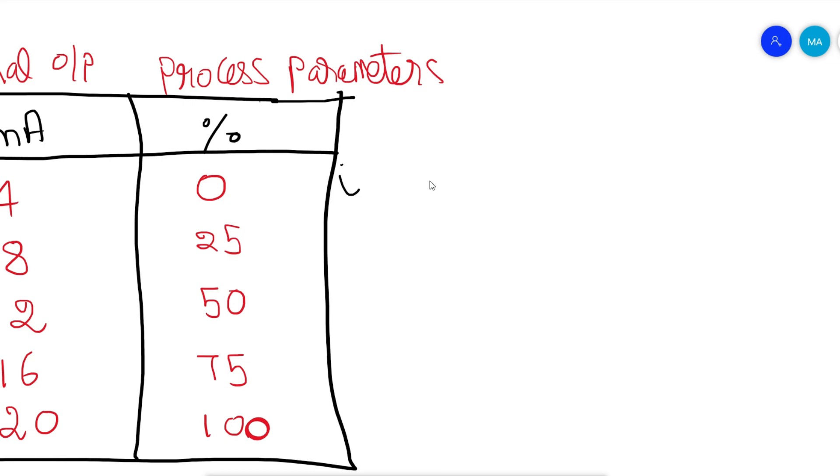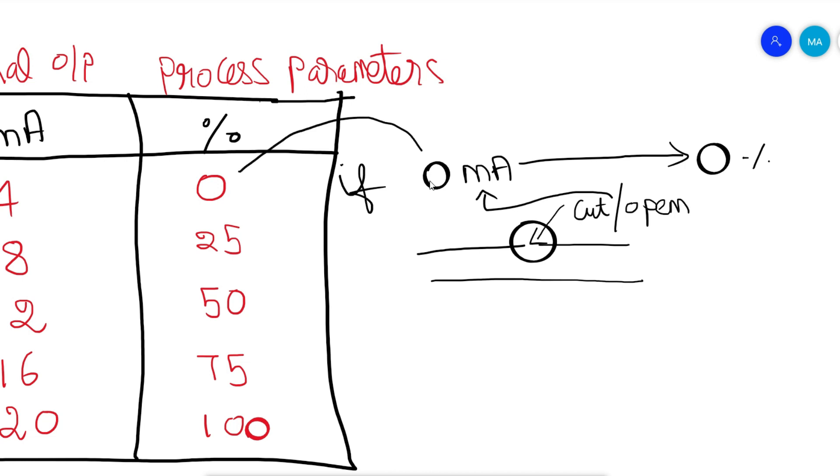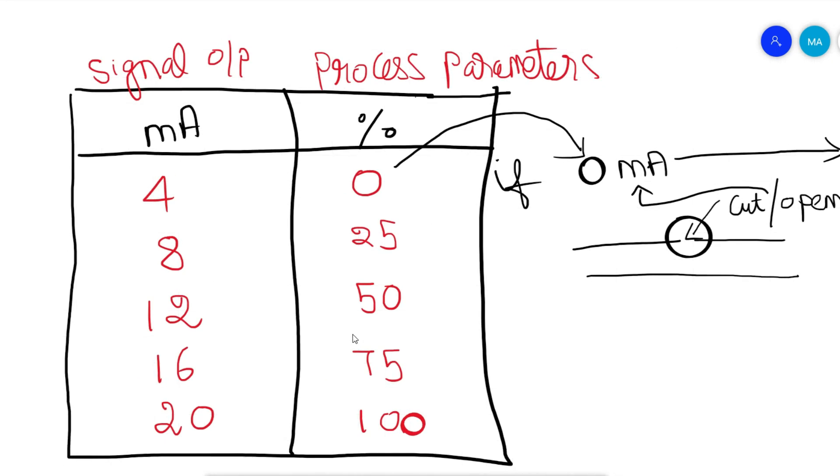You could easily find that if an instrument signal shows zero milliamps, it means there is no power supply in the instrument signal cable. There might be a possible signal cut or cable open. If we are using zero milliamps for zero percentage, it would misguide us to show that there is a zero percentage process parameter.